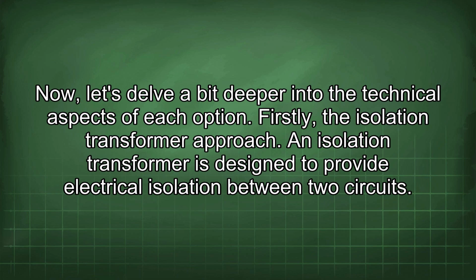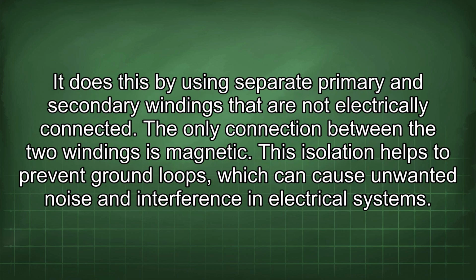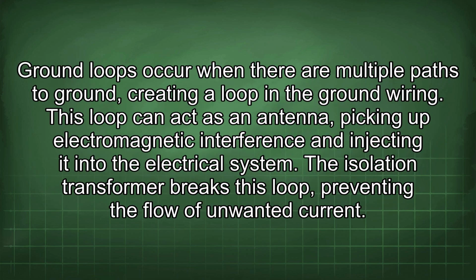Firstly, the isolation transformer approach. An isolation transformer is designed to provide electrical isolation between two circuits. It does this by using separate primary and secondary windings that are not electrically connected. The only connection between the two windings is magnetic. This isolation helps to prevent ground loops, which can cause unwanted noise and interference in electrical systems. Ground loops occur when there are multiple paths to ground, creating a loop in the ground wiring. This loop can act as an antenna, picking up electromagnetic interference and injecting it into the electrical system. The isolation transformer breaks this loop, preventing the flow of unwanted current.